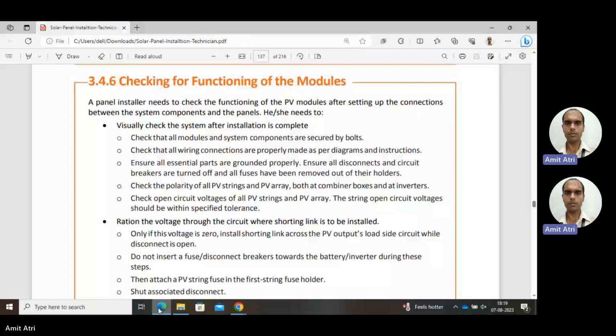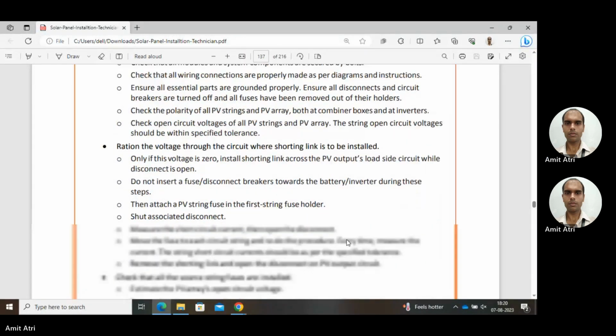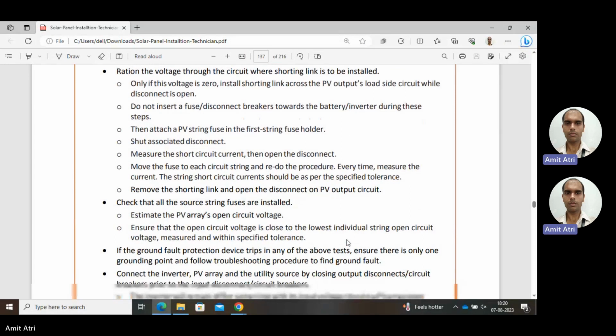So next, the installer needs to measure the voltage through the circuit where the shorting link is to be installed. So only if this voltage is 0, then install the shorting link across the PV output load side. Okay, while the side circuit that is open, means it is on no load, open circuit mode. So next, we do not insert a fuse or disconnect breaker towards the battery inverter during this step. Means maintain isolation. Then attach a PV string fuse in the first string fuse holder. In the sequence we have to move. The next, shut the associated disconnect. Then measure the short circuit current.